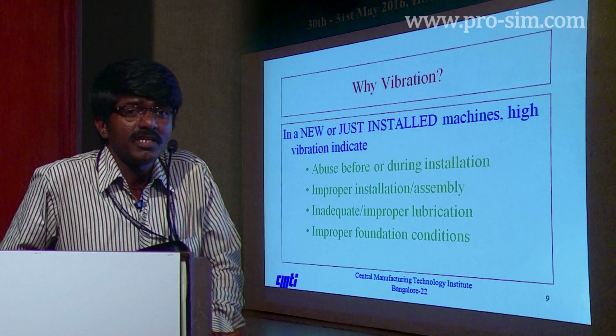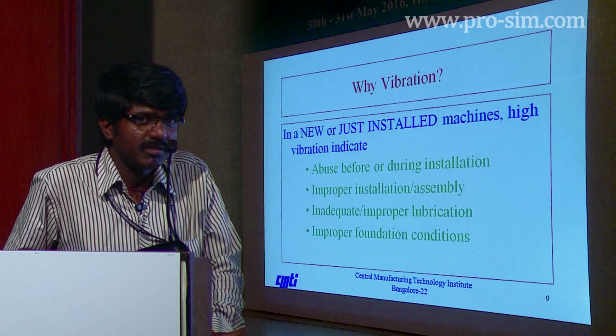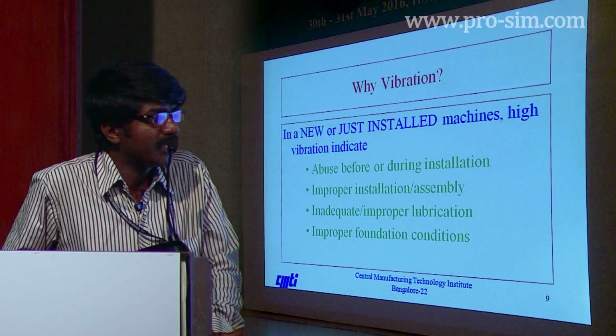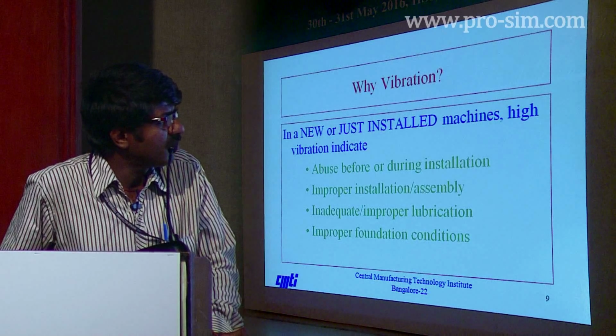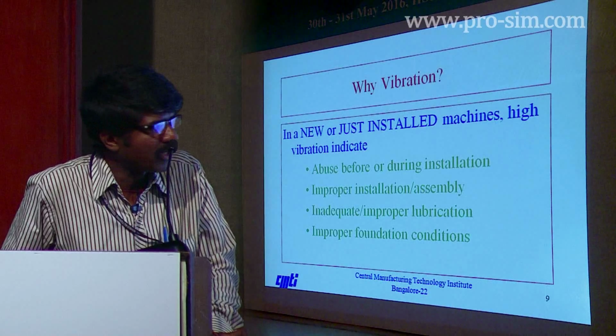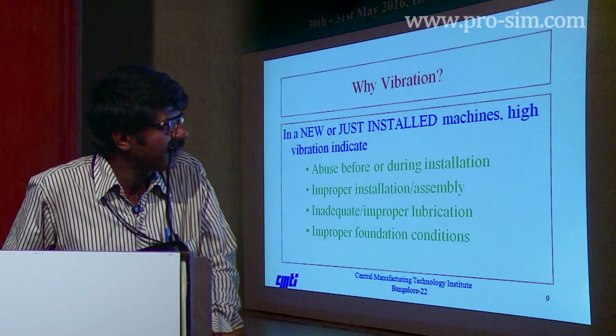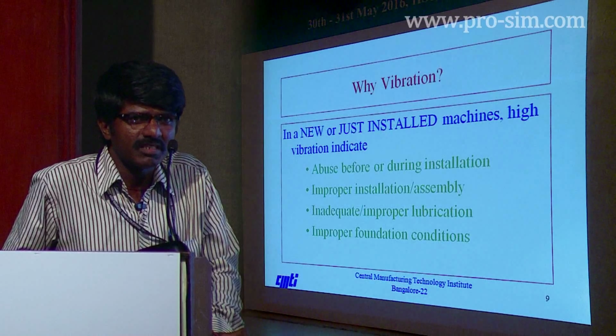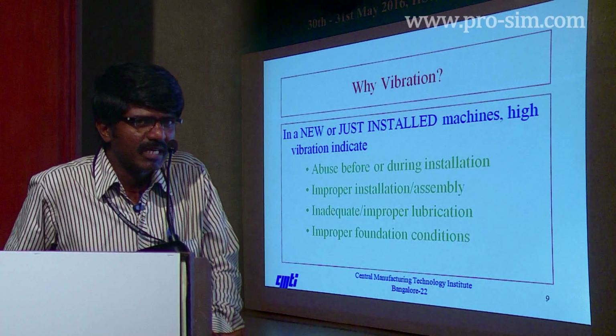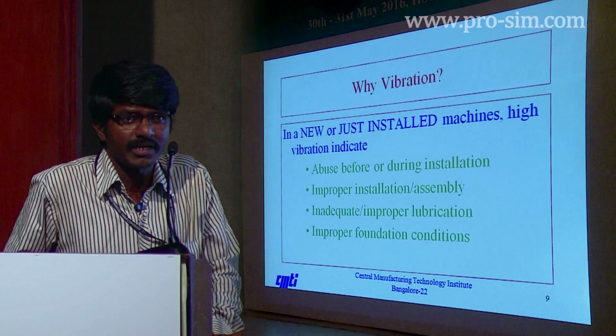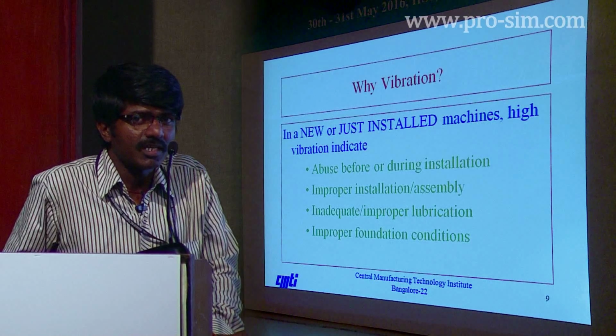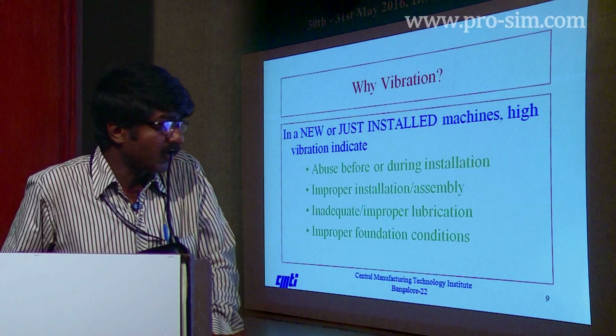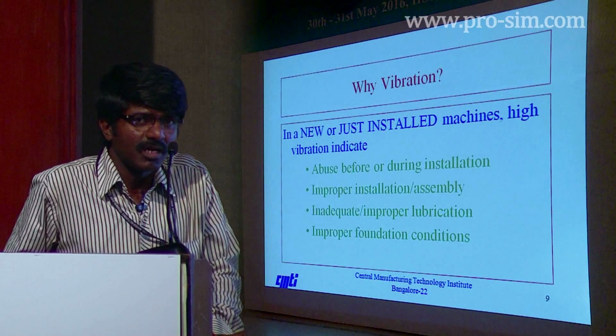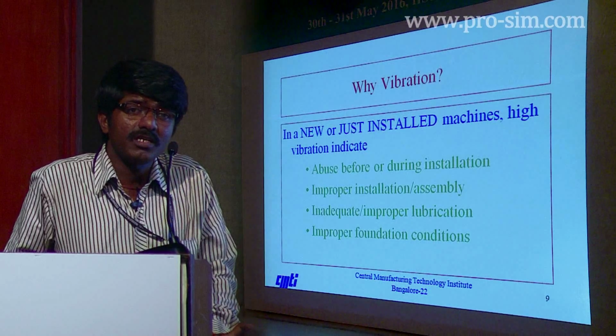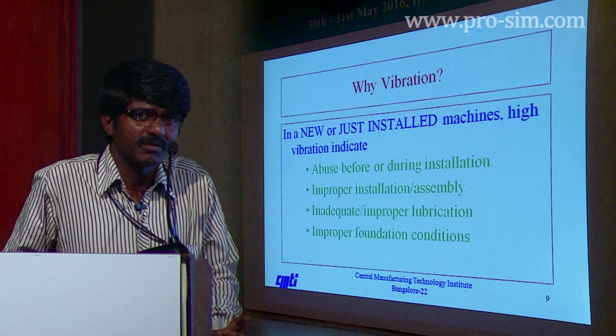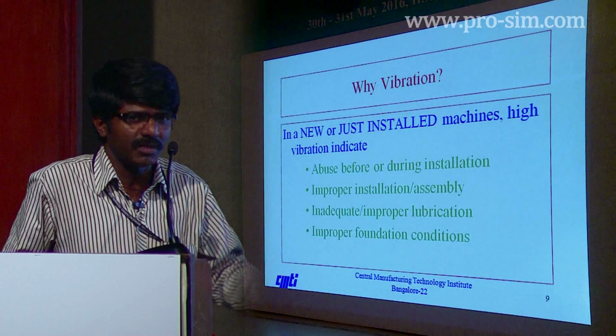So it doesn't mean that new machines will always give less vibration. Sometimes they may give more vibration also, because of these reasons. Abuse before or during installation, improper installation, or incorrect assembly will give higher vibration. Assembly errors mean new machines will also generate higher vibrations. Inadequate and improper lubrication, or an improper foundation, will also give higher vibrations. It is influenced by these parameters.